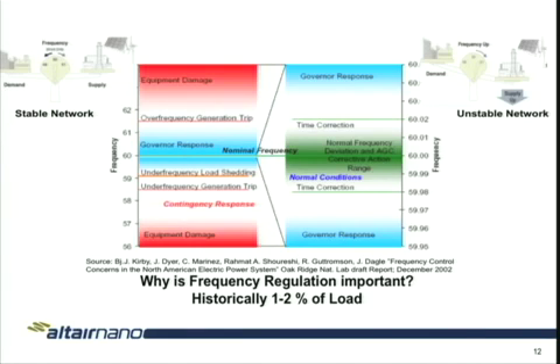And then down at the lower end, you might have too much load, maybe a line tripped to a generator, maybe one of the nuclear plants tripped offline, and suddenly you have all this load but no generation, and things start slowing down, just start bogging down to control that. And as you go through those periods, you have a governor, as you're moving around 60, you have a governor response, over frequency generation trip, equipment damage, and downstream under frequency load shedding, under frequency generation trip. But in the middle here, you have a lot of what's called spinning reserve and frequency regulation.